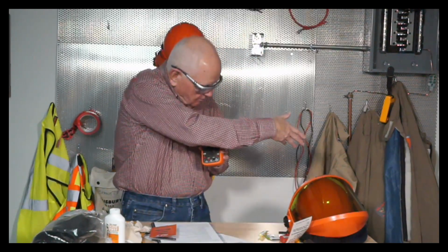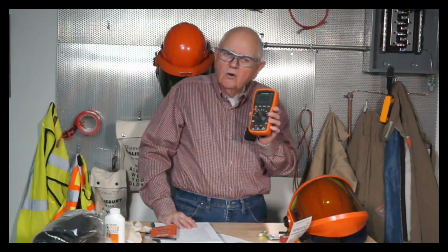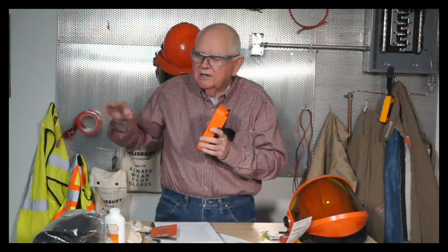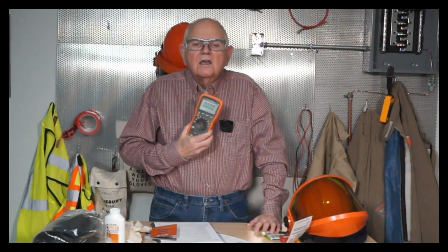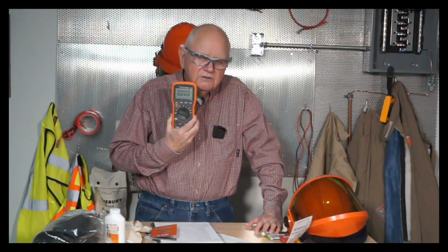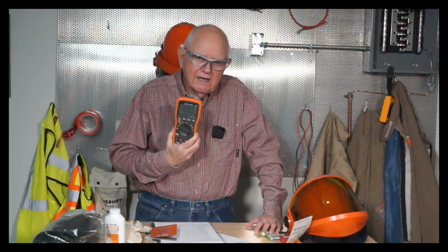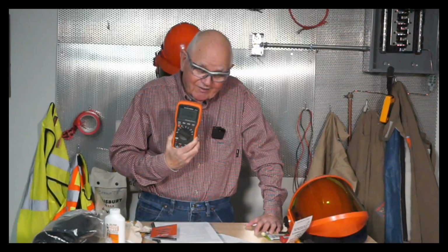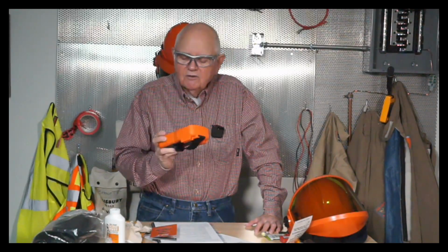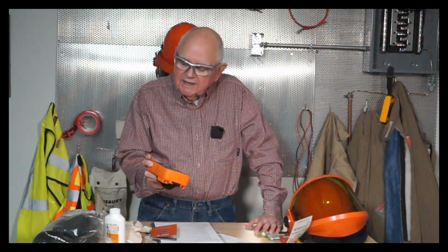Category 2, I'm just going to read the branch circuit right over here, the end of my branch circuit at the receptacle. Category 3, I'm going to go out in my plant out here and I'm going to read maybe 480 volts or whatever it is in my system. Category 4, I need to go outside and take some readings, maybe out by the service or something like that. It's all based on surge protection. The more category I have, the more surge protection I have. Okay, most of your meters, if you take a look, you've got good quality meters out there. They're probably rated, this one is rated for Cat 3, 1000 volts, Category 4, 600 volts.